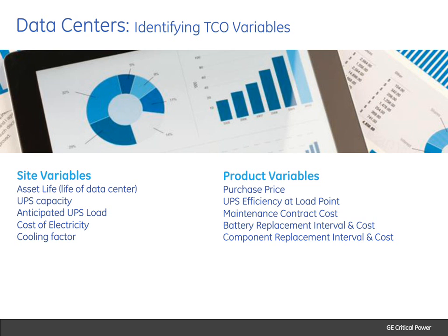The last variable is what we call the cooling factor. As we talked about earlier, UPSs generate heat, and that heat needs to be removed from the equipment room. The cooling factor is how efficient the cooling system is in removing that heat from the room, and that has to be factored into the TCO model. A good proxy for this is PUE. If you think about the PUE metric most of us know, that's a good proxy to understand how effective the cooling system is at removing heat from the room. A PUE of 2.0 would not be particularly efficient by today's standards, but many data centers are often operated at that level. If you operate at 1.1 PUE, you have a very efficient cooling system.